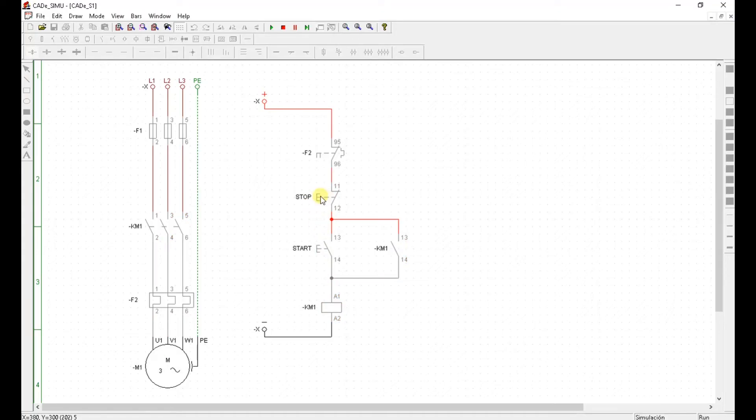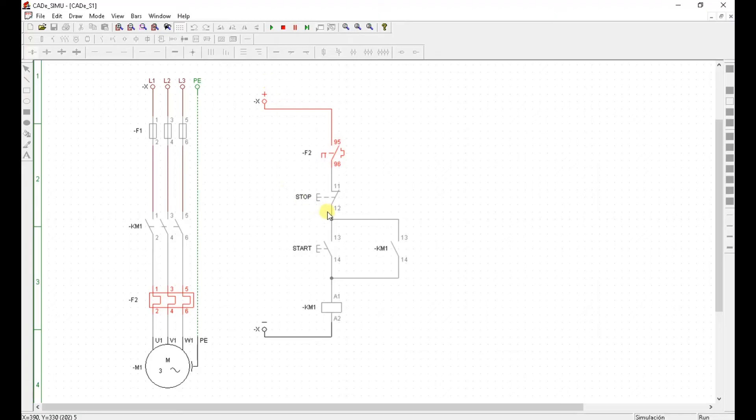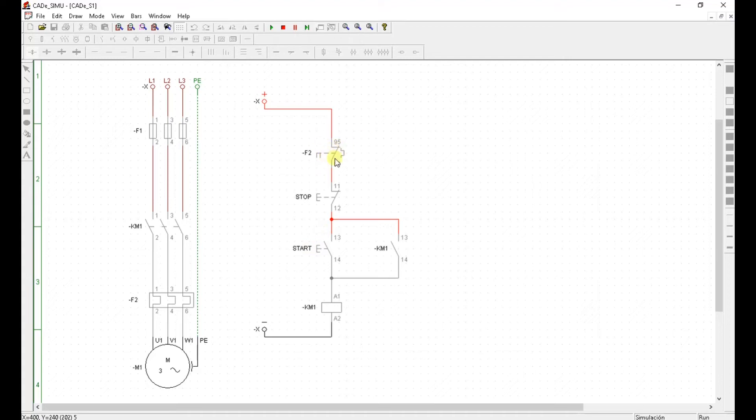OK. We can simulate two other things. For instance. I can simulate overload. If I click on F2. You'll notice that this auxiliary contact of heat relay become open. Once it become open this path is broken. And the KM1 is no longer energized. OK. Let me restore the power. Clicking on F2 again. And then you'll notice that this contact become closed. Press start. There you go. Motor is running fine again.